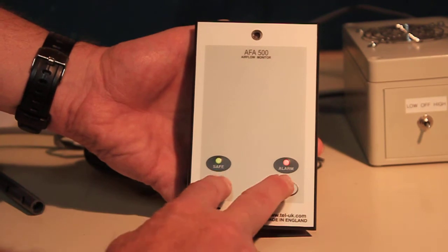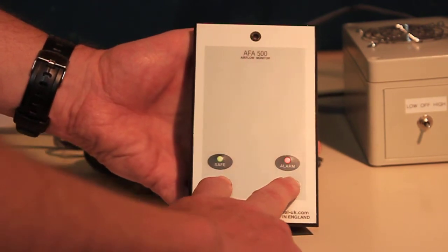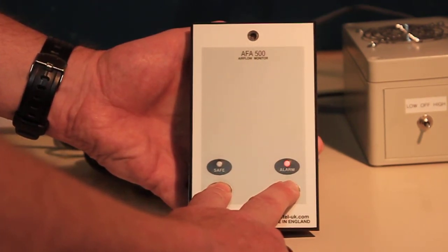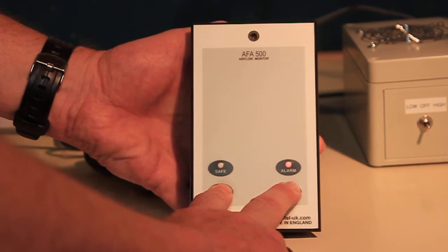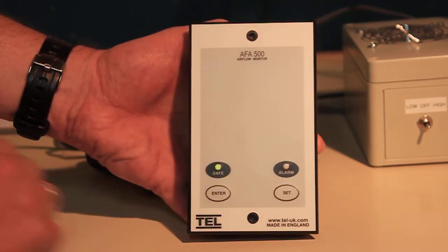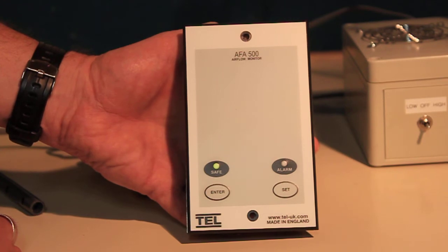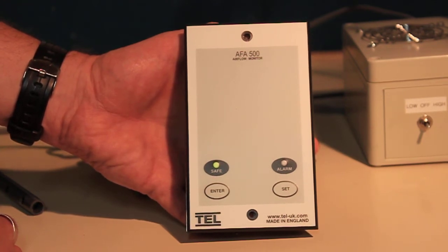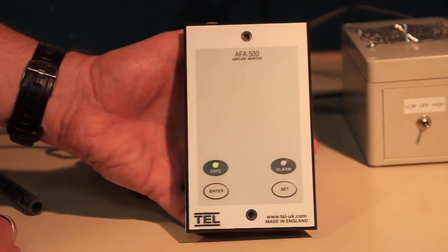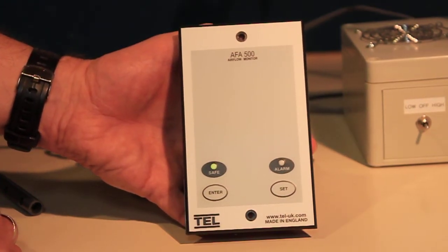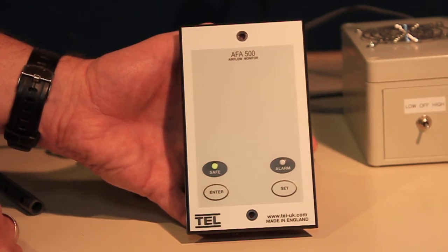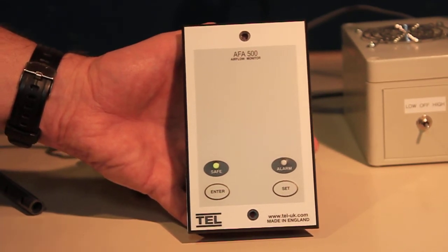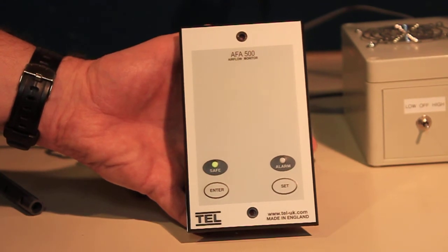To initiate calibration, press and hold the Enter and Set buttons at the same time. The unit will sample the airflow for 5 seconds, during which time the green LED goes off and the red LED flashes. The audible alarm continues to sound during the air sampling. If the Enter or Set buttons are released during the air sampling period, or if the airflow is fluctuating too much, the alarm will emit a lower frequency buzzing for a short period and then re-enter calibration mode. If this occurs, press the Enter and Set buttons again to repeat the airflow sampling.